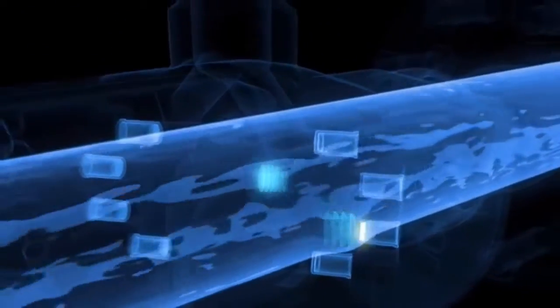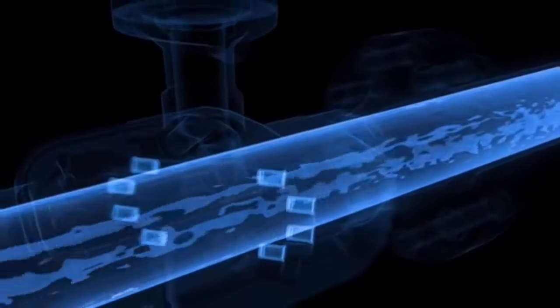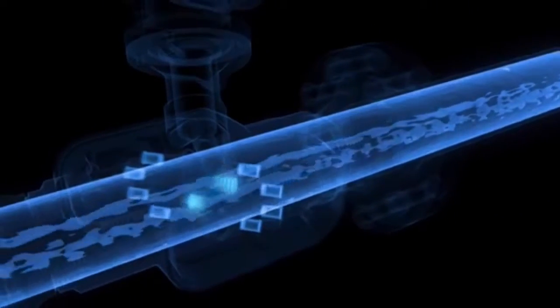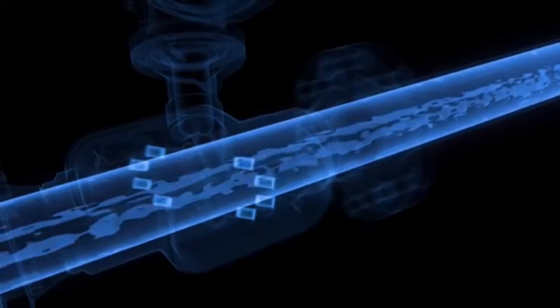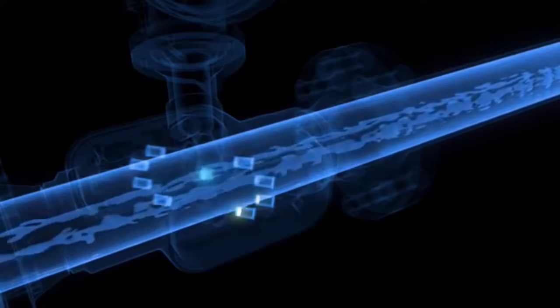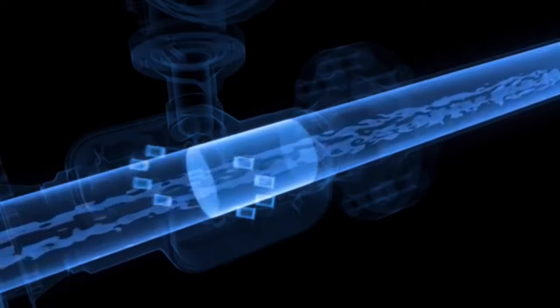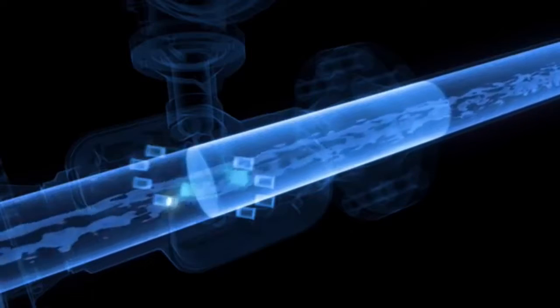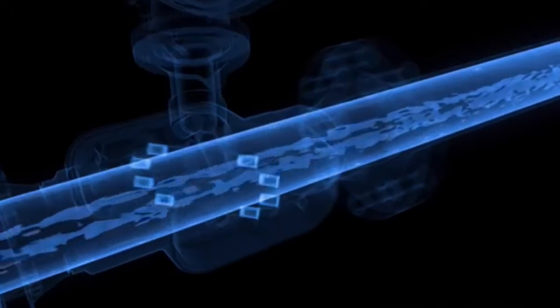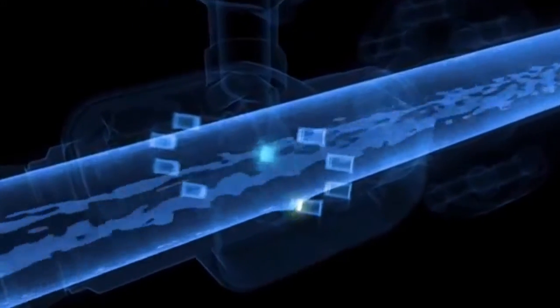Therefore, the times measured by the sensors are directly proportional to the flow velocity inside of the pipe. Together with the known cross-section, the actual flow volume can be calculated. The greater the time difference, the greater the flow velocity.